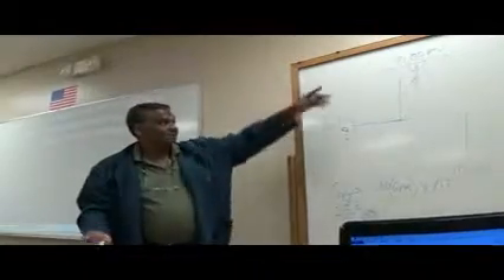There's always a drain cock there, right? Yeah, you open it and check how many gallons per minute. Because if I need 3 gallons per minute, I need 1 GPM here, 1 GPM here, 0.5 here and 0.5 there. It ain't hard to check 1 gallon per minute, with a gallon bucket and stuff, that's how we do it.